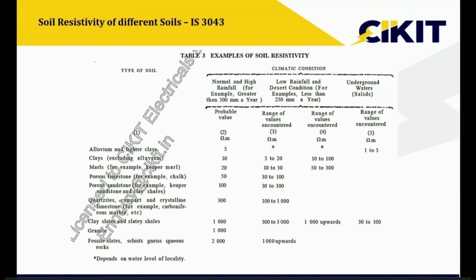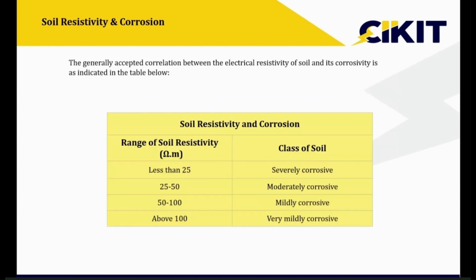This is the table of soil resistivity values provided by the standard IS 3043 for different types of soil. If you observe this table, they have provided the soil resistivity value based upon the moisture content. The first value is for normal and high rainfall, whereas the second one is for lower rainfall. From this table you can observe the impact of moisture level on the soil resistivity values.